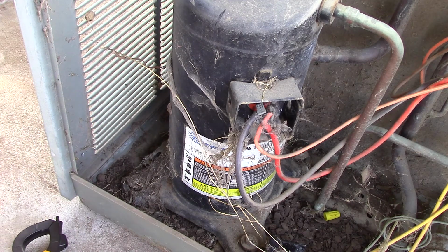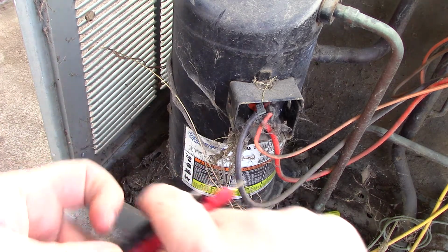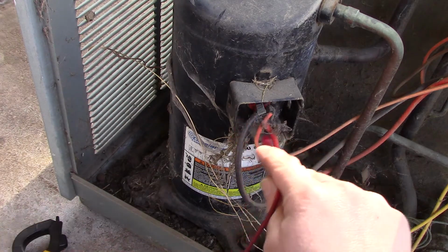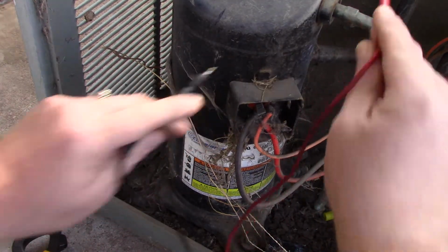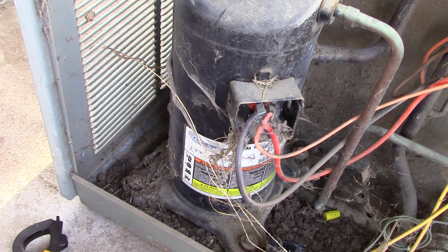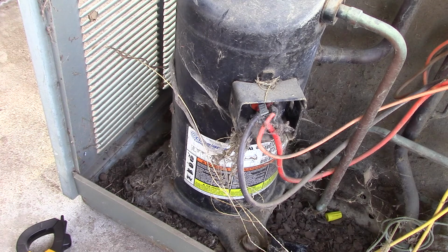You also want to check too, if you've got a megohm meter or a meter like mine that does megohms, pull all those connections off, go terminal to ground, and see what the megohms are. If your megohms are, let's say, 1.4 million ohms, this thing is going out. It's on its last leg. It's just a matter of time. If it's 30 million ohms, well, you've got some life in it still, but don't expect to get 20 years out of it. You can maybe expect 5 years, provided you keep up with the maintenance on everything. So there's some information on troubleshooting compressors and ohming them out.